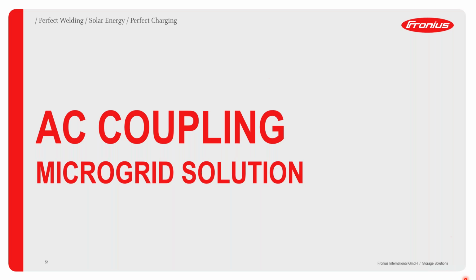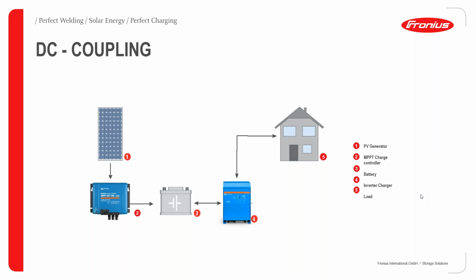Having talked about the Fronius Gen 24 inverters, let's now look at the AC coupling concept, or what we call the microgrid solution. As already mentioned, if you are living in an area that is lacking in grid stability, or where the grid keeps on failing from time to time, you might want to think about an AC coupled kind of configuration, and this allows you to go into off-grid operation for longer durations of time.